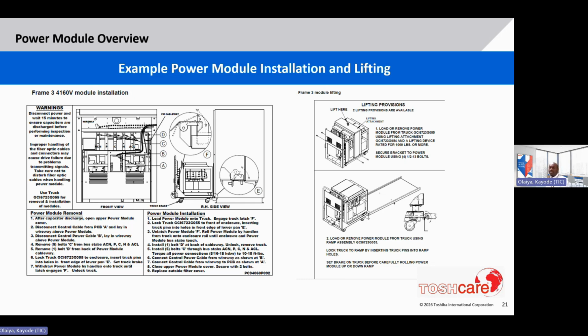There are instructions on the door of the power module explaining the steps to pull them out, and it mostly involves disconnecting the cover for the control cables and the bolts for the cables that are connected to the module, and the bolt that holds the module to the frame. Depending on the frame size, the bolts are located at different places. And then the module racks out.